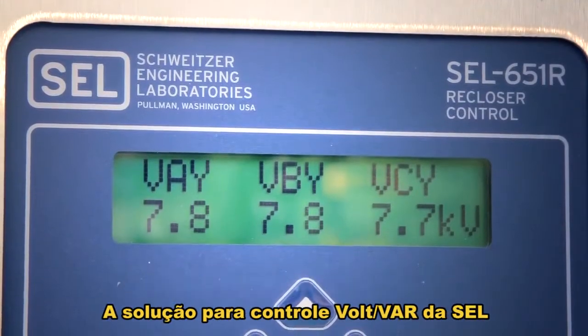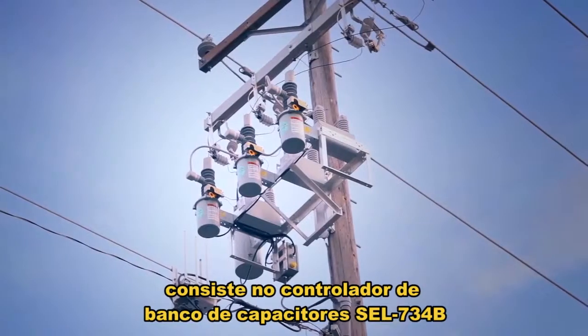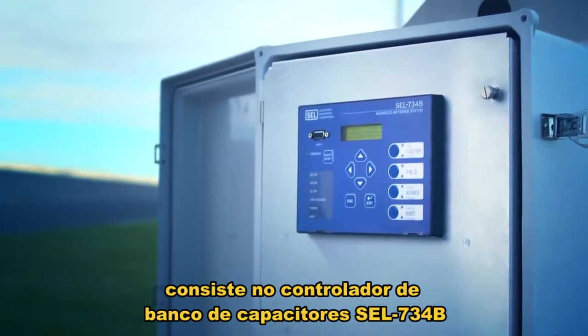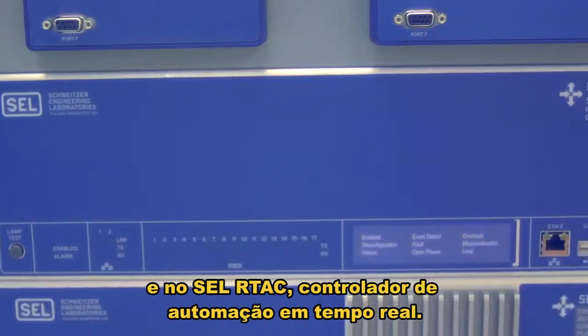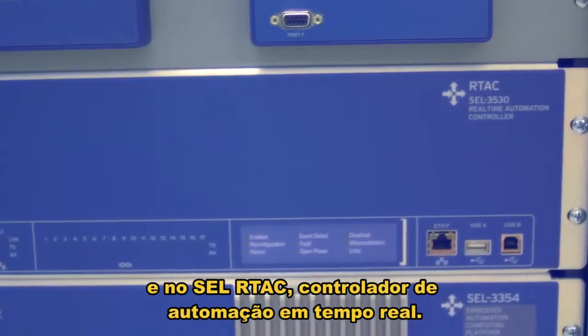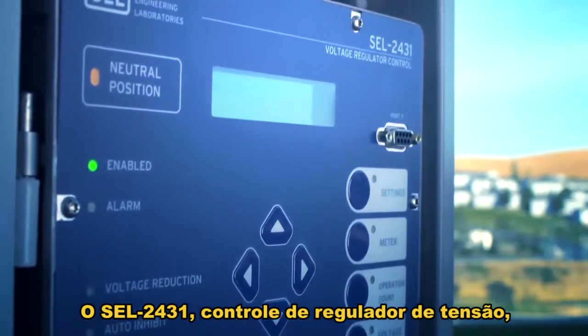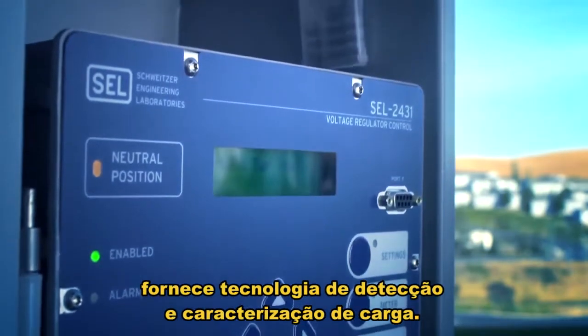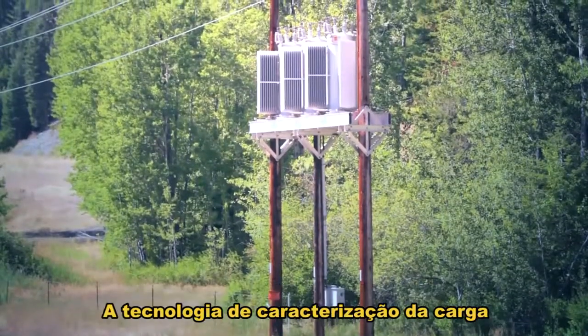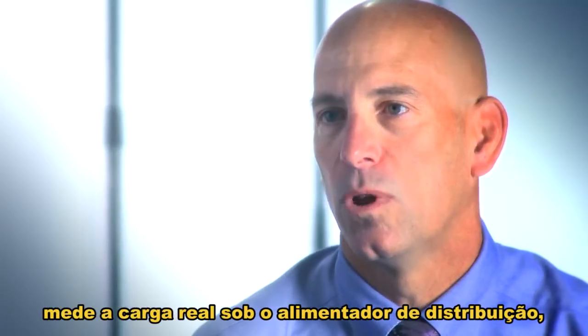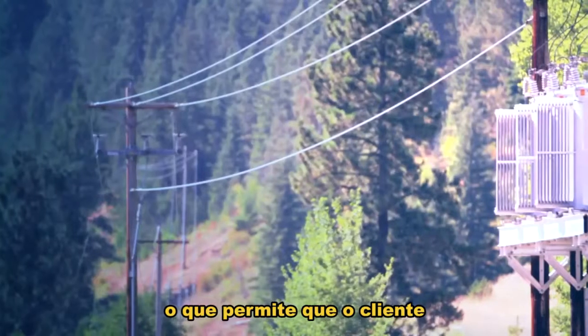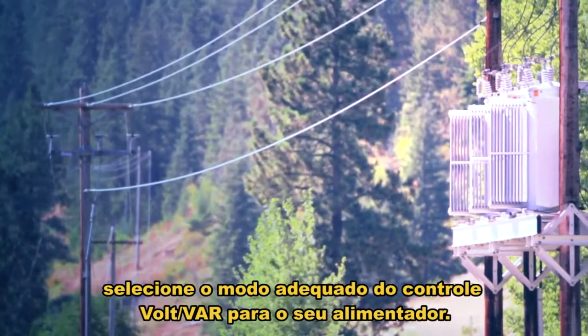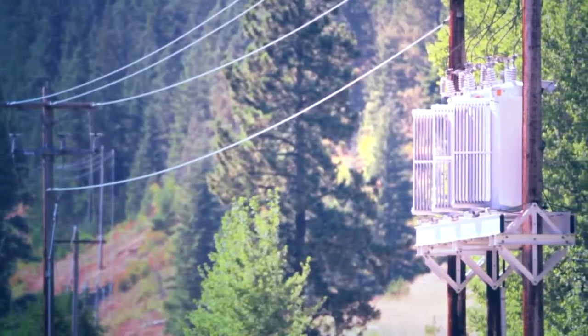hugely popular for that. SEL's volt VAR solution consists of the SEL 734B capacitor bank control and the SEL RTAC real-time automation controller. The SEL 2431 voltage regulator control provides load sense technology. The load sense technology measures the actual load on the distribution feeder, which allows the customers to select the proper volt VAR control mode for their feeder.